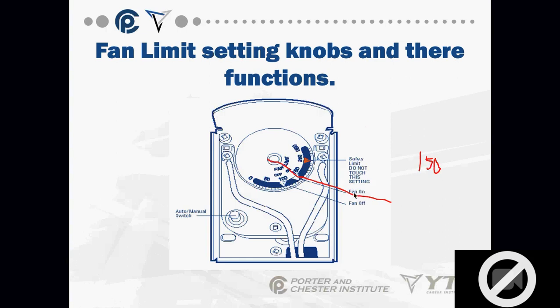Okay? If the fan does not come on, or if I don't have enough airflow for the equipment, the limit on this one is set for 200. If the limit of 200 is reached, it's going to turn the burner off. We get no more heat source. It will cool down. Okay? When it gets usually back down to roughly where the fan on is, it will turn that burner back on. So you can have a system that's not blowing air around the house, that's actually bouncing on and off on high limits.